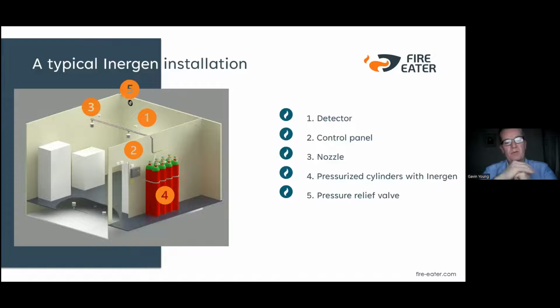And you also need a pressure relief valve, which is a pressure relief damper. So generally, we focus on maybe two different levels of pressure relief in terms of structural strength. The risk is either 200 pascals or 500 pascals of pressure that the structure can maintain. If you discharge the system into a risk without a pressure relief damper, the fear is that a wall will come down or a door would open and you won't hold the gas within the risk for the 10 minutes, and a fire could reignite.